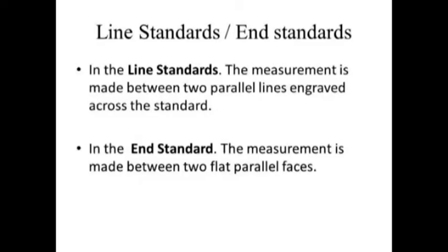So in the line standards, when the length is measured as a distance between the centers of two engraved lines, it is called a line standard. So both material standards, yard and meter, are line standards. The most common example of line measurements is the rule with divisions, as shown, with lines marked on the instrument. Okay, so these are the line standards.